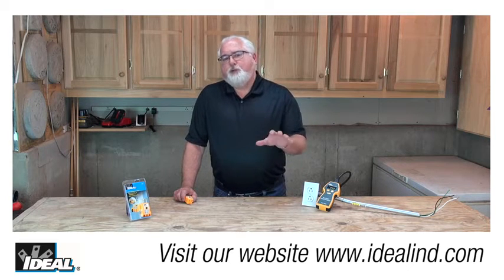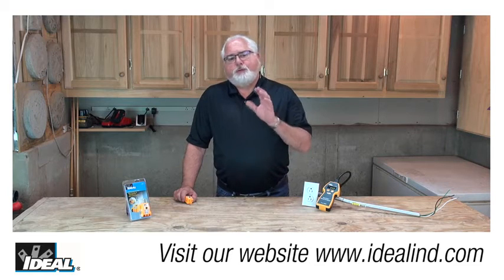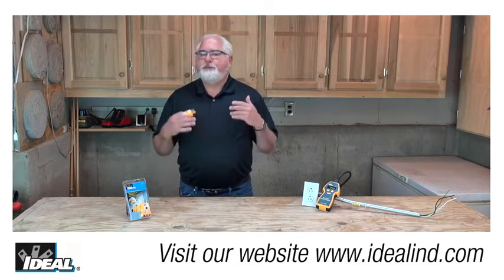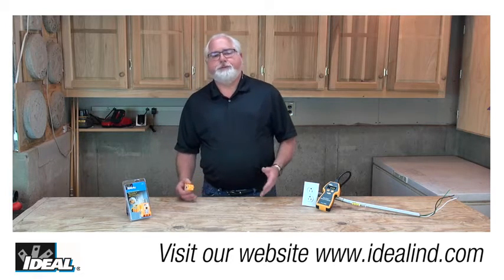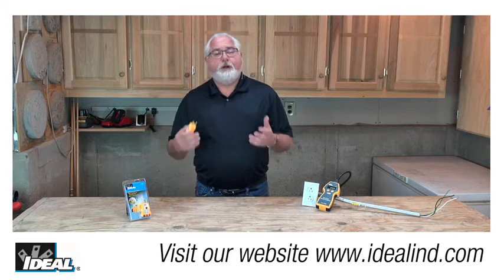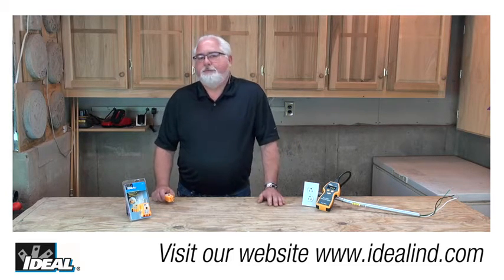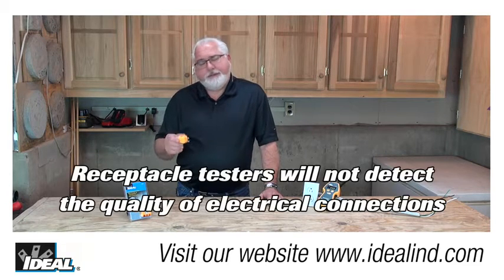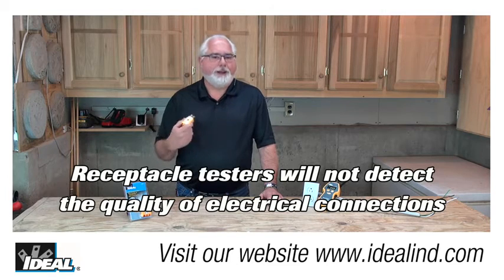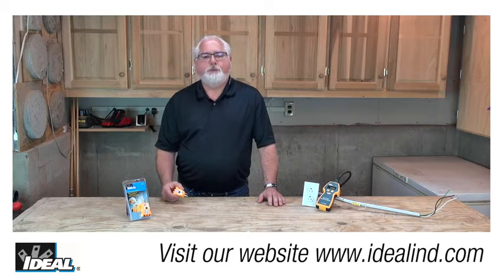Now, a few words of caution, folks, about receptacle testers, and that is receptacle testers are simple, inexpensive, and very useful, but you also have to be aware of their limitations too. And that's generally true with all types of receptacle testers you see out in the market, not just the Ideal 61-501. And that is that this type of tester can't tell you anything about the quality of the electrical connections behind the walls. Now, it doesn't take much power to light the little bulbs up.